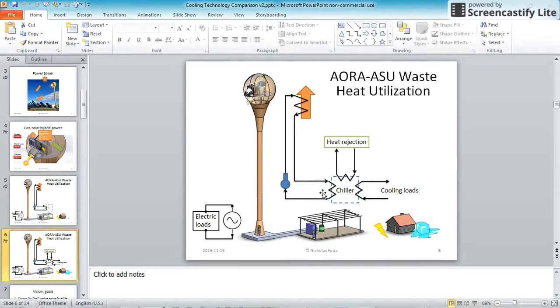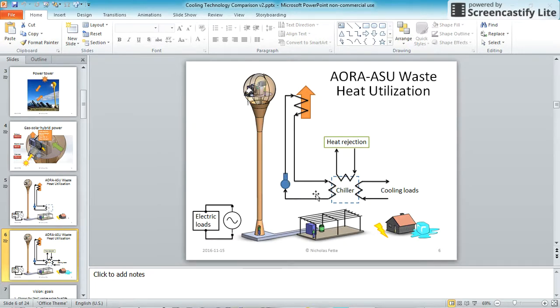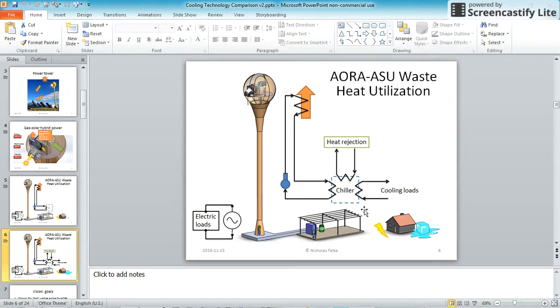In terms of comparison, what I wanted to do is optimize a given chiller for the design conditions. So what is the ambient temperature? What is the temperature and flow rate in the heat source? I would adjust the values of these heat exchanger areas to get the most cooling for a given amount of cost.